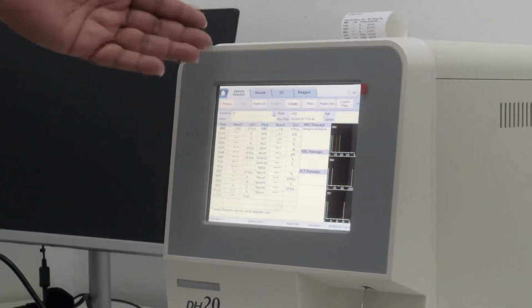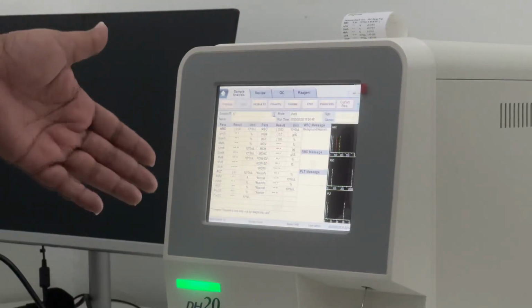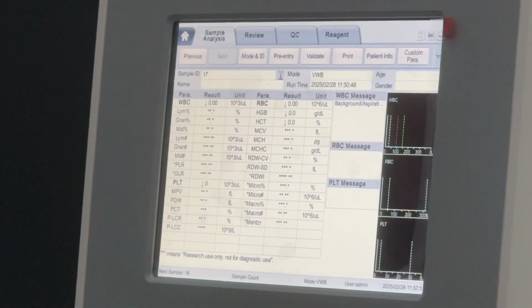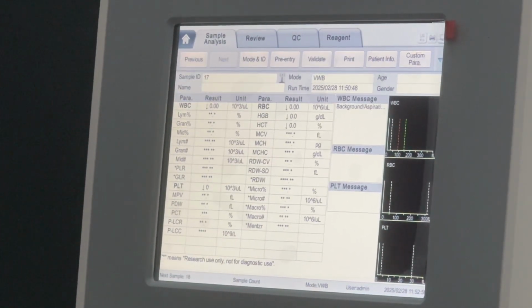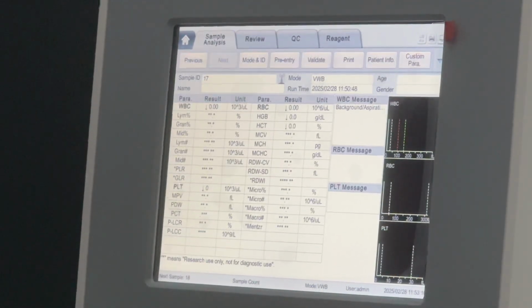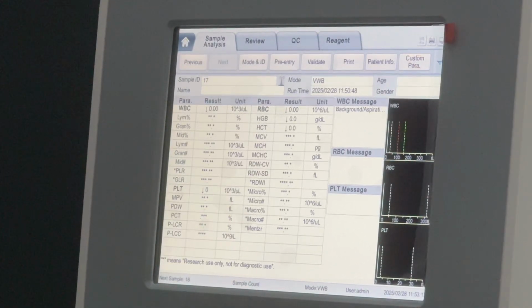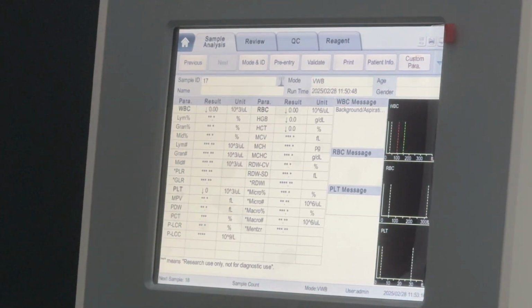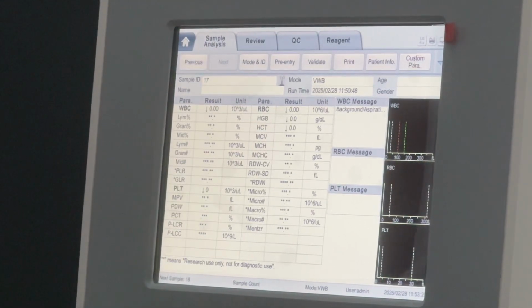Okay, and I come back to the result when it comes to blank count. If you see over here, everything is zero and star. It shows that the machine is detecting. Okay, it's a blank count. The default setting starts from zero. If the machine goes wrong, the default setting may be more than zero, sometimes 10 or 20, something like that. So now everything is in the default setting, so the machine is okay. So now we can run the sample.